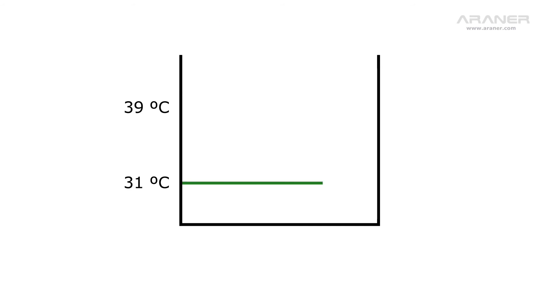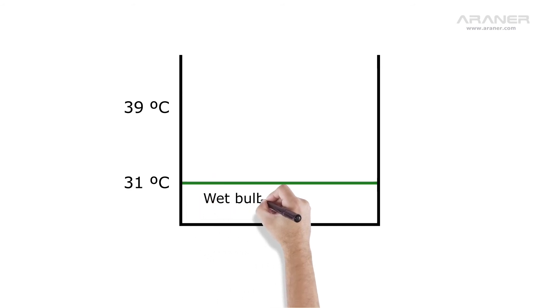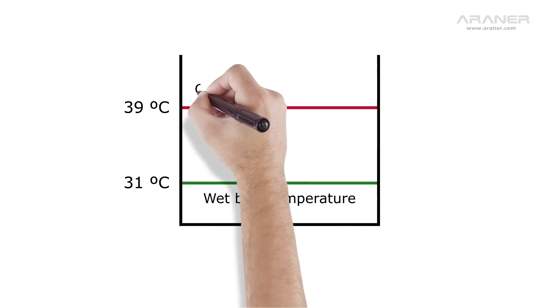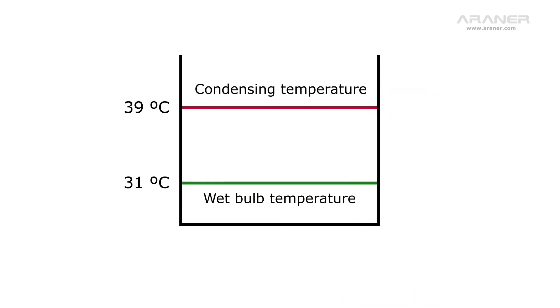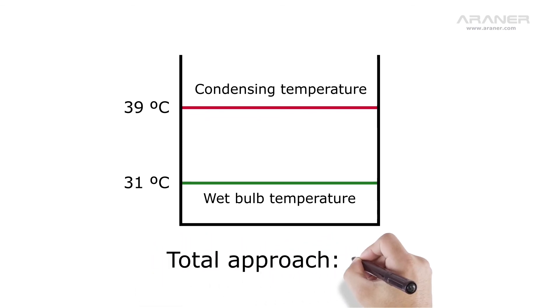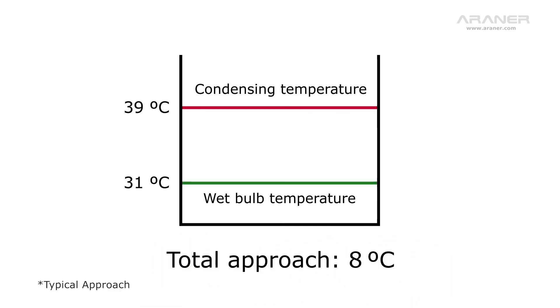Starting also from 31 degrees of wet bulb temperature, we will be condensing lower at 39 instead of 41, because we eliminated the water temperature difference of the cooling water loop, resulting in a total approach of 8 instead of 10.